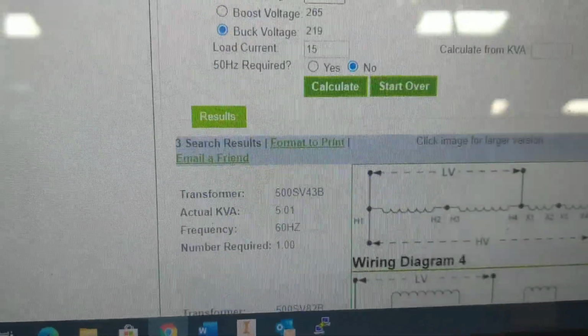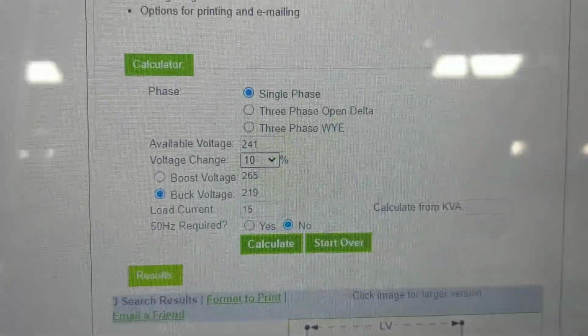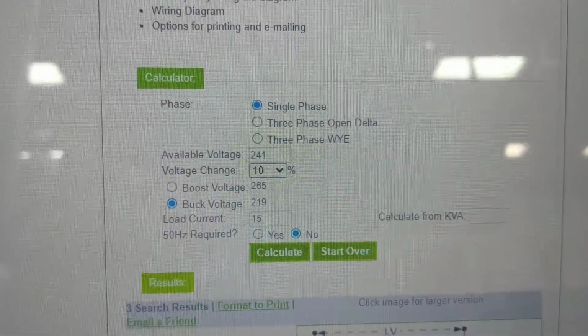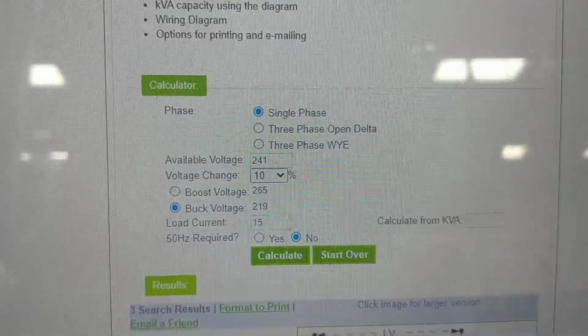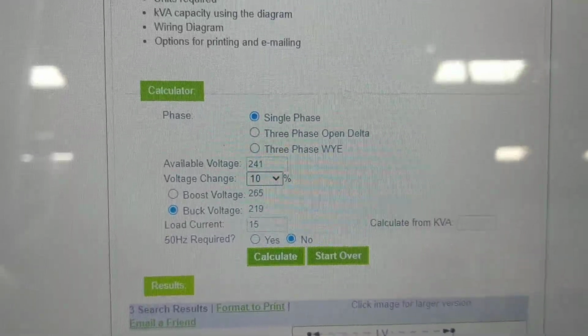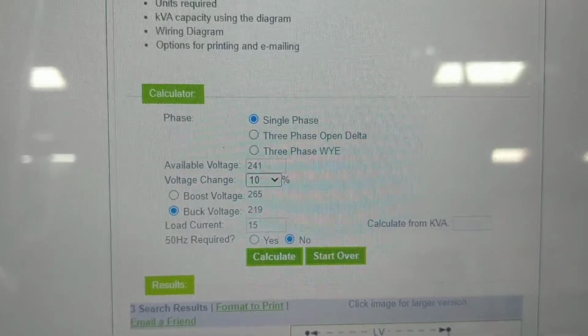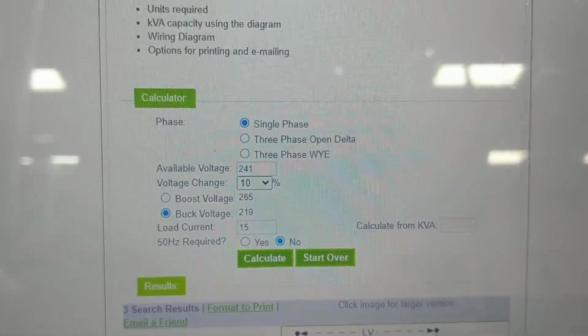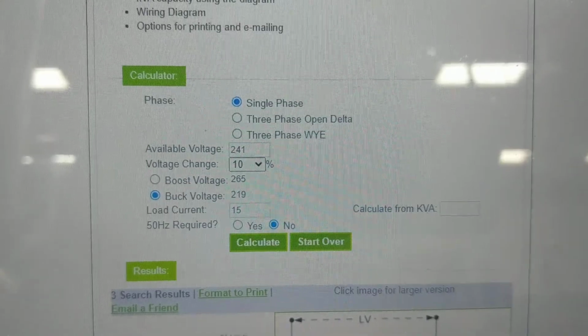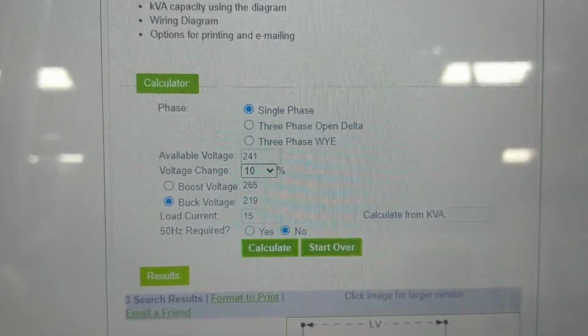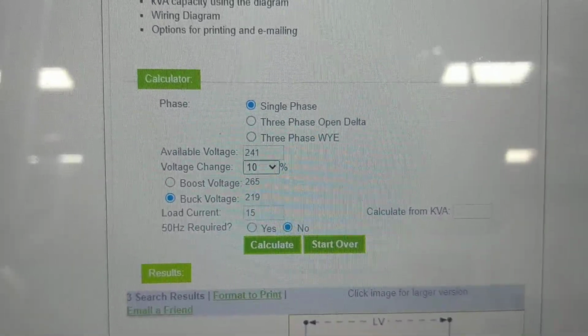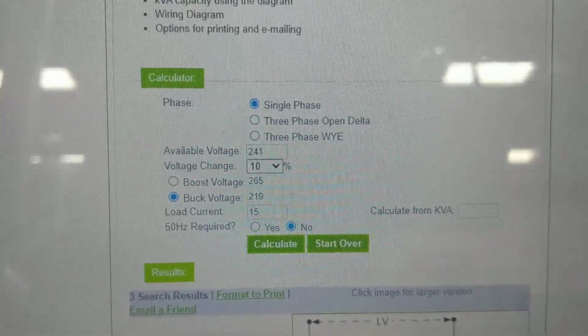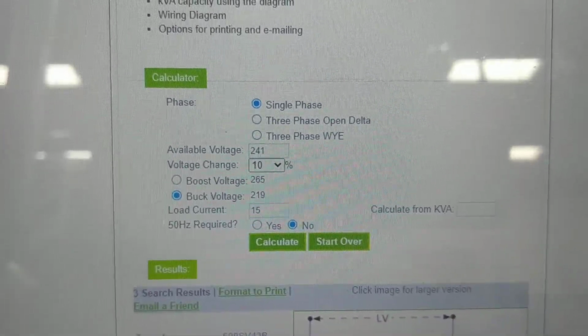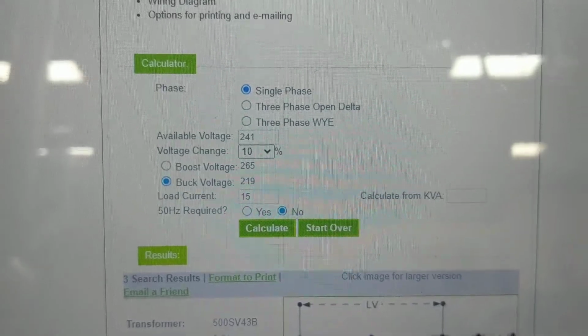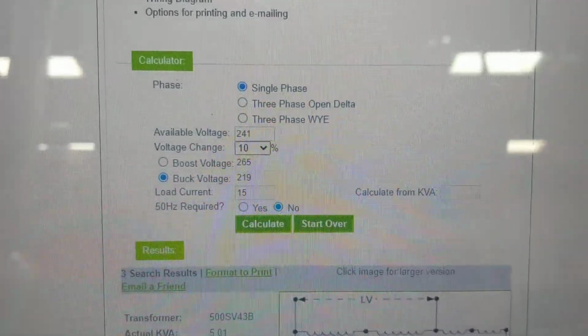What's important is plugging in your specifications. For single phase power, I put the available voltage at 241 volts, with a voltage change of 10%, which is about where I wanted to be. I chose to do what's called buck voltage, lowering the voltage by 10%, which takes me down to around 219 volts with a load current of 15 amps.